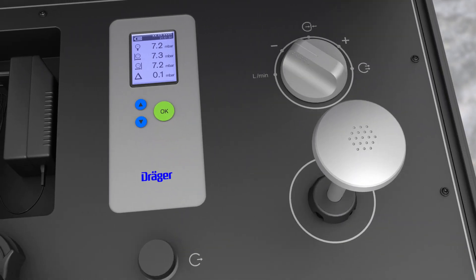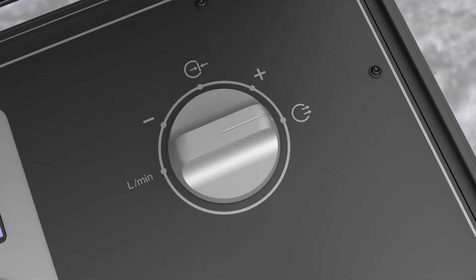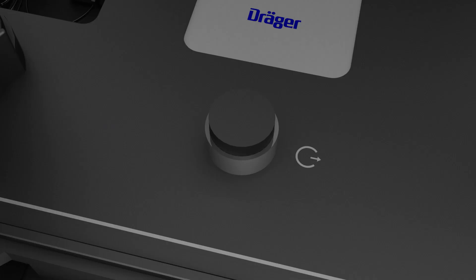You can easily change to negative pressure and flow meter, or use the quick venting mode to vent your PSS-BG4. To decrease the pressure, simply press the button which offers slow and medium venting to help you achieve your required pressure.